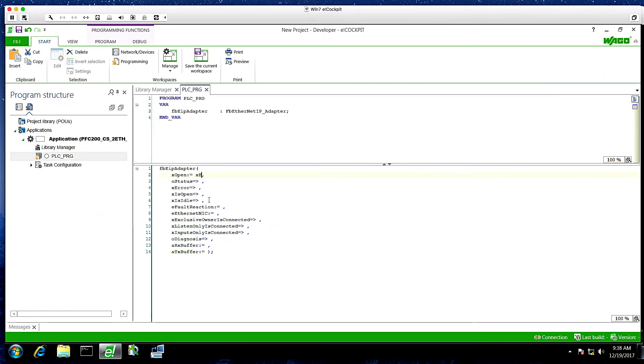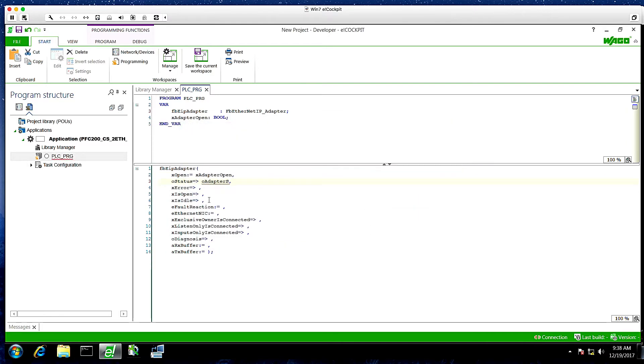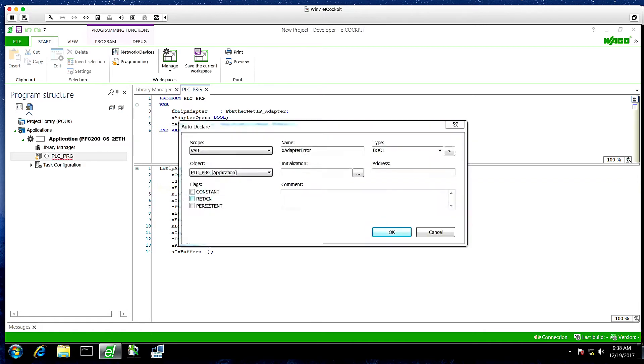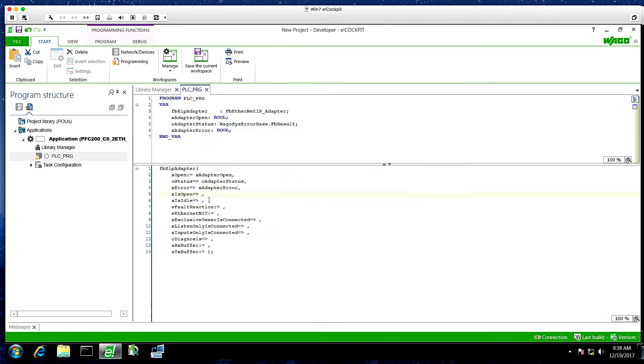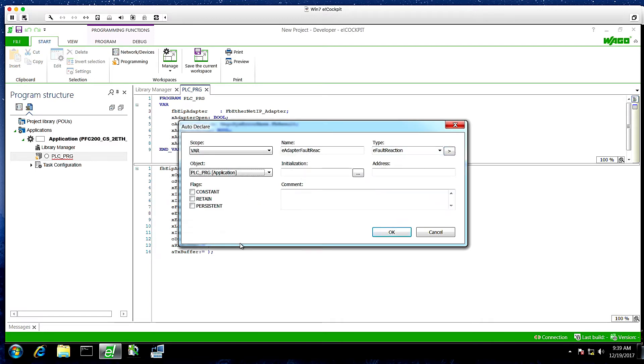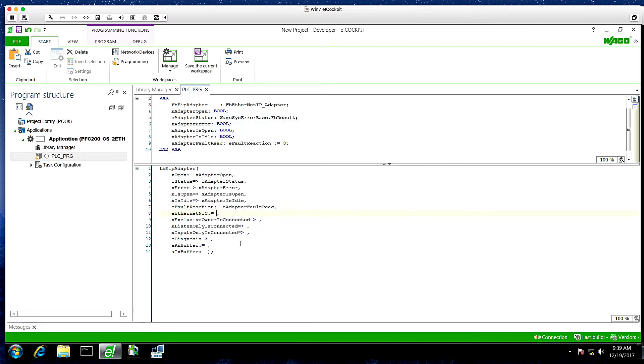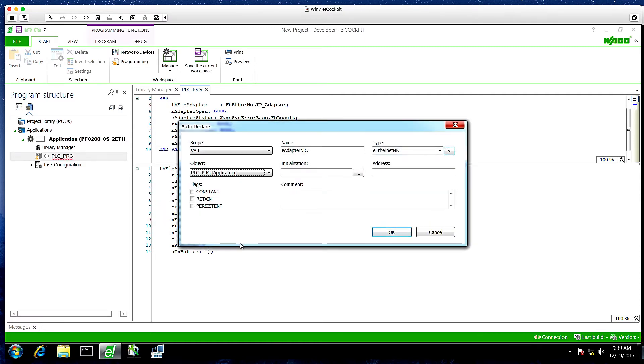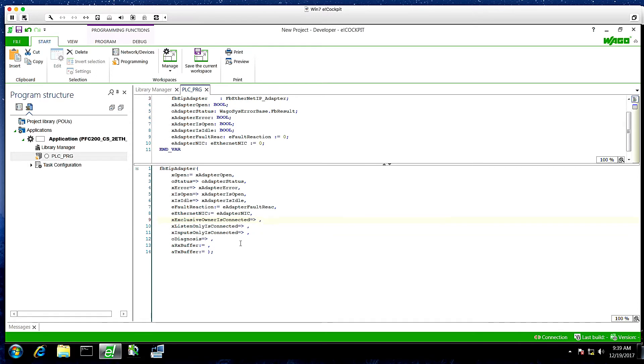So if we create variables in these fields, they'll adopt the variable type that we need. We'll start with adapter open. We'll add an object adapter status. Adapter error. A boolean for is open. Another boolean for is idle. We'll add the enumeration for the adapter fault reaction. And we're going to initiate this with 0, which means everything will go to 0 if it loses comms. And then we'll add the NIC as well. And the NIC will also initiate at 0, which will use just the switched ports.